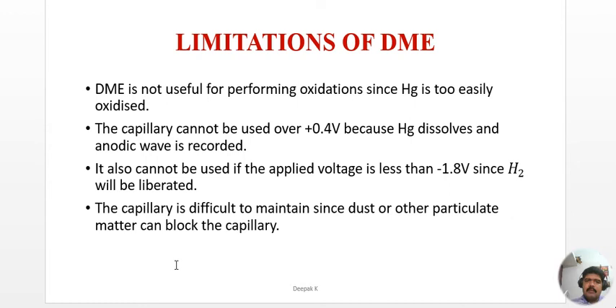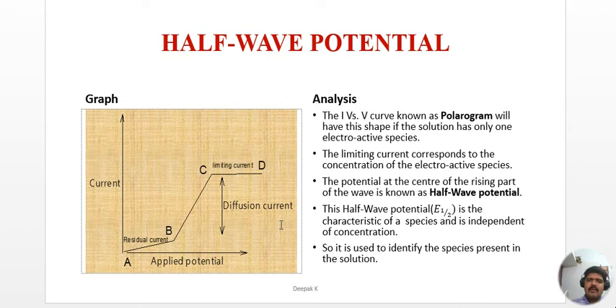Limitations of the DME: mercury can be too easily oxidized, so it cannot be used for oxidations. The capillary cannot be used above +0.4 V because mercury dissolves and an anodic wave is recorded. It cannot be used below −1.8 V since hydrogen will be liberated. Also, the capillary is difficult to maintain as dust or particulate matter can block it.